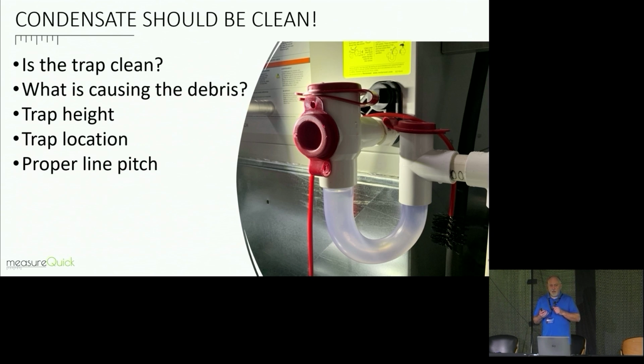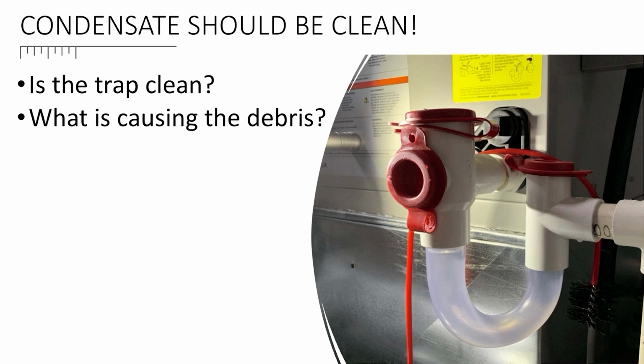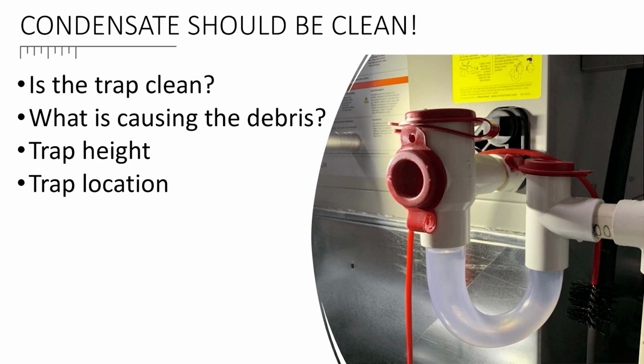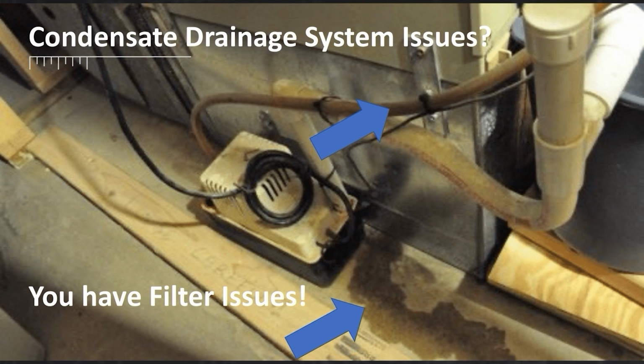And if you're not finding an underlying cause, which is dirt bypassing the filter, undersized filtering, you should never have to clean it. So you've got to figure out what's causing the debris, make sure your trap height's good, make sure your trap location's good, make sure you have proper pitch. Condensate drainage issues, you likely have filter issues, right? And that's what this is here.